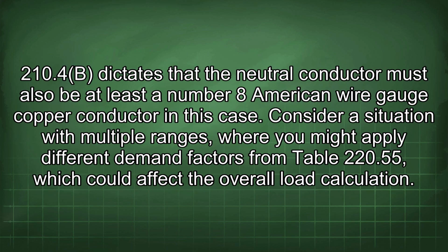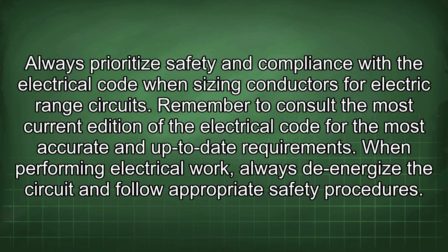210.4b dictates that the neutral conductor must also be at least a number 8 American wire gauge copper conductor in this case. Consider a situation with multiple ranges where you might apply different demand factors from Table 220.55, which could affect the overall load calculation. Always prioritize safety and compliance with the electrical code when sizing conductors for electric range circuits.